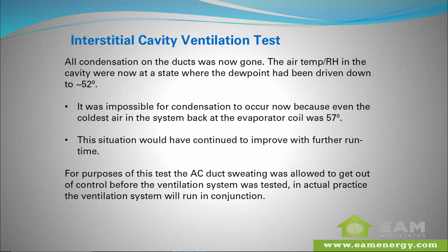The other thing to note here was that we had really allowed the system to get out of control, worst-casing it in terms of the duct sweating. In actual practice, the ventilation system would run in conjunction with the AC system, and so we really never would have allowed it to even get to that point where it was beading and dripping sweat, condensation all over the place.